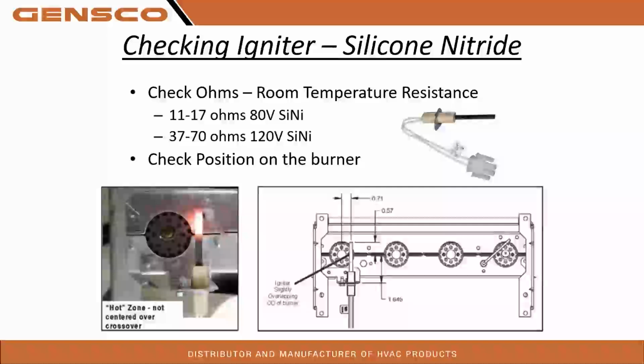You're also going to check positioning on the burner. I know some guys were big on those Fireflies. They're great products, great universal to have on your truck, but you have to make sure you get that hot spot in the right spot. Otherwise, you're going to have heavy lighting or no lighting at all, and eventual lockouts and homeowner discomfort. So if we can, we want to provide the manufacturer specific igniter because it'll sit in the exact spot it's supposed to be and light that furnace off. If we go into universals, we need to make sure they are hitting where they need to hit. There are two different positions for these igniters, and we'll show them. But we need to make sure we're hitting the hot spot.